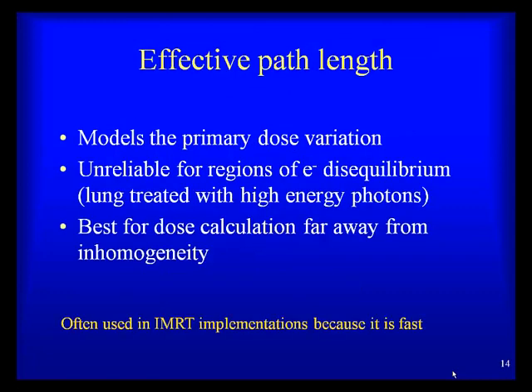Effective path length is one of the early methods for addressing inhomogeneities. It models the primary dose variation. However, it's unreliable for regions of electronic disequilibrium where density or atomic composition changes and the electron spectrum changes traversing from one medium to another. It usually gives good results when the calculation point is far from the inhomogeneity. Because of its simplicity and speed, effective path length techniques have often been used in IMRT implementations and are still used as such.